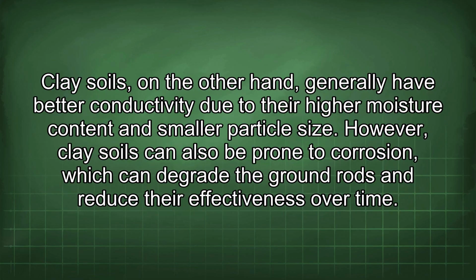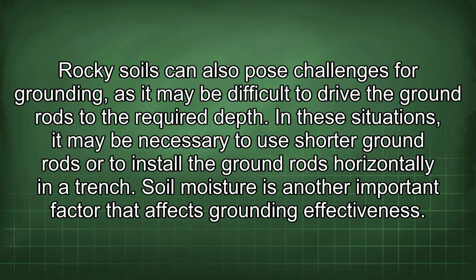Clay soils, on the other hand, generally have better conductivity due to their higher moisture content and smaller particle size. However, clay soils can also be prone to corrosion, which can degrade the ground rods and reduce their effectiveness over time. Rocky soils can also pose challenges for grounding, as it may be difficult to drive the ground rods to the required depth. In these situations, it may be necessary to use shorter ground rods or to install the ground rods horizontally in a trench.